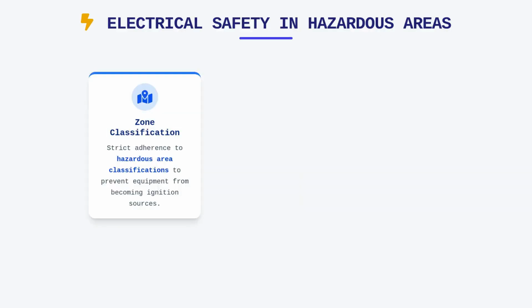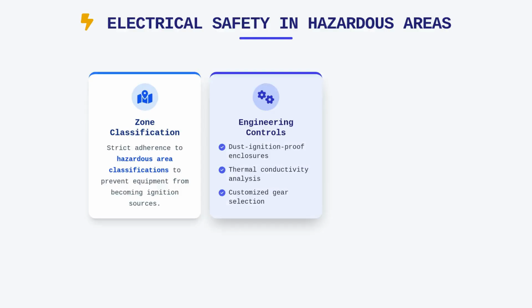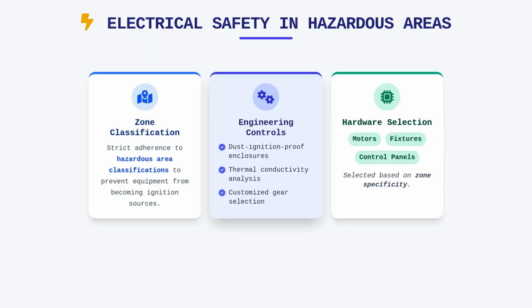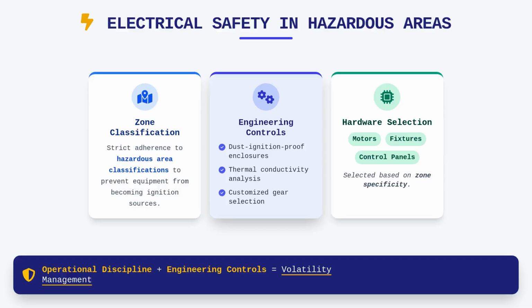The electrical configuration of these facilities requires strict adherence to hazardous area classifications to ensure that no equipment serves as an ignition source for the surrounding dust. This involves using dust ignition-proof enclosures and avoiding dust-tight installations that fail to account for the unique thermal conductivities of the material being processed. Every motor, light fixture, and control panel must be selected based on the specific classification of the hazardous zone. This systematic application of engineering controls, combined with operational discipline, is the only way to manage the volatility of an industrial environment where combustible materials are handled at scale.